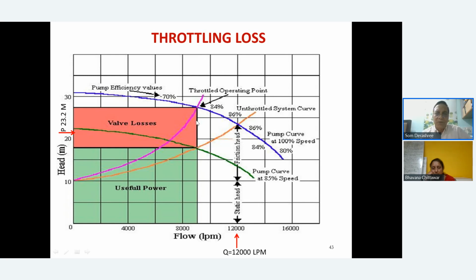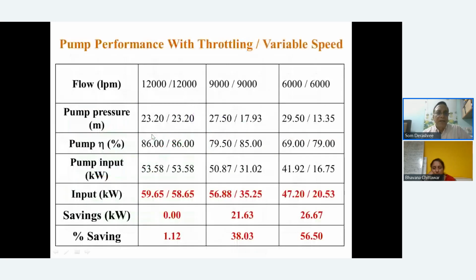This is the amount of loss which has happened, because you could have, supposing you were here on this line, then you needed only the 9,000 flow. This could also be achieved if you had a lower diameter of the pump, or maybe a lower speed of the pump. Then also you can reduce that. That will give you this much amount of saving. This is a typical case of throttling versus the variable frequency drive, you see.